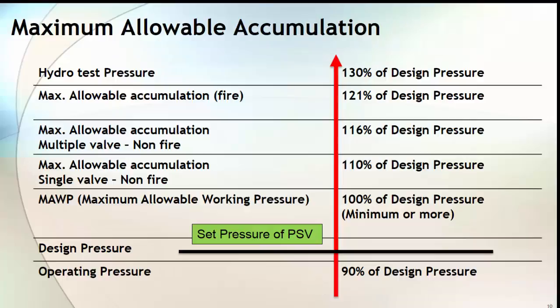Now look at this table, which shows maximum allowable accumulation based on the number of PSVs mounted on the equipment and also on fire and non-fire type of equipment. If your equipment is fitted with a single valve and is non-fire type, the maximum allowable accumulation is 110% of design pressure. If fitted with multiple valves, the maximum allowable accumulation is 116% of design pressure. In case of fire type equipment, the maximum allowable accumulation is 121% of design pressure.